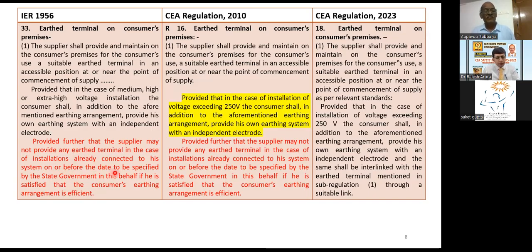The state government can fix some date because there are a lot of existing installations, and the state government is the entity to look into the safety of the general public at large. Because safety always comes under the state subject in the constitution, the regulatory authorities have left this discretion to the state government. And as per regulation 2010, you can see the same thing. Here, one more thing they have refined from 1956. What they have refined is that the supplier should provide the earthing up to 250 volt consumers. If the voltage exceeds 250, then the consumer should provide his own earthing system, independent.